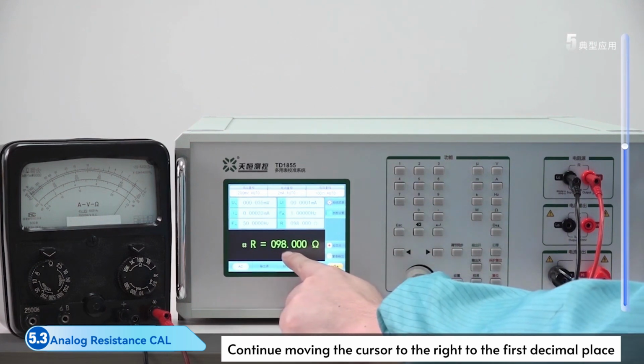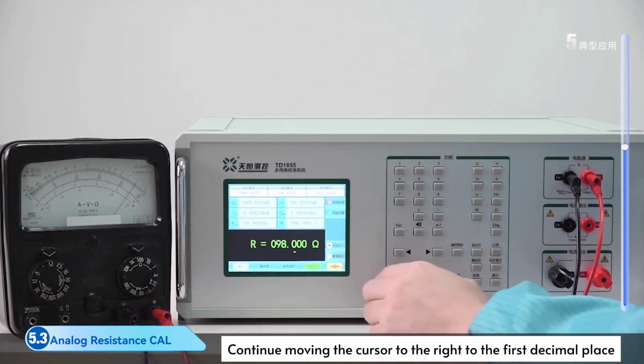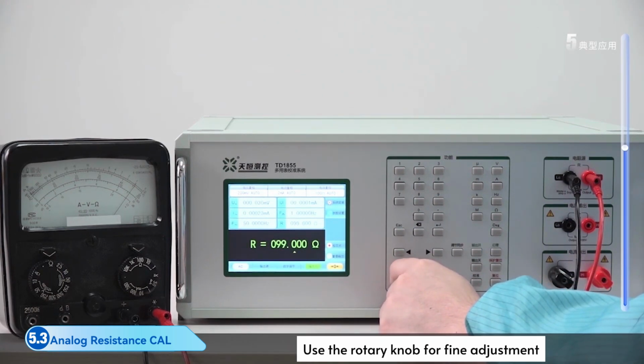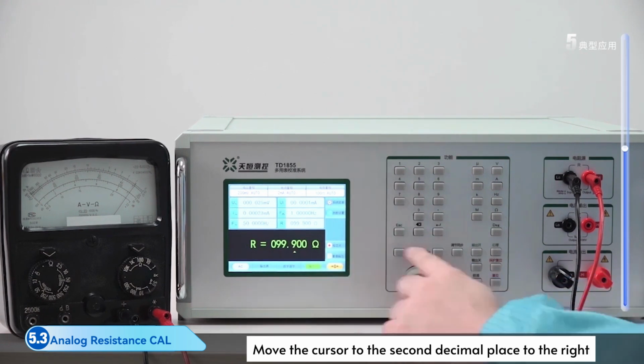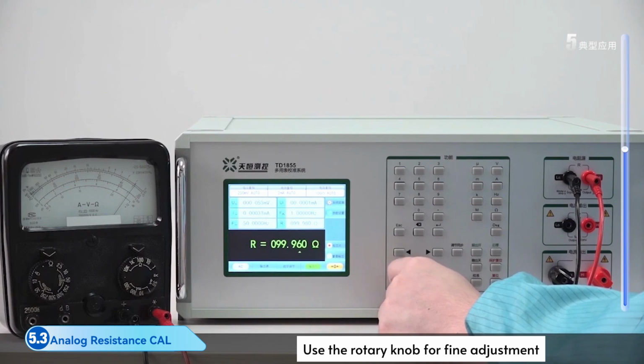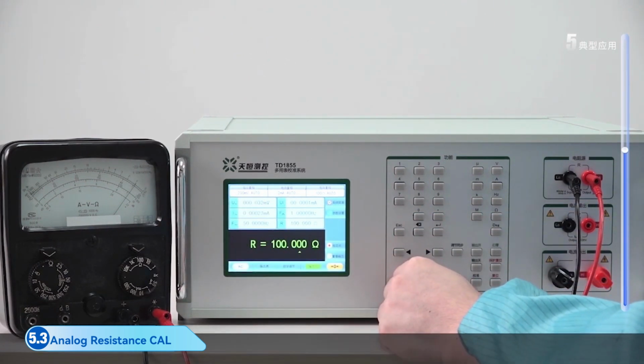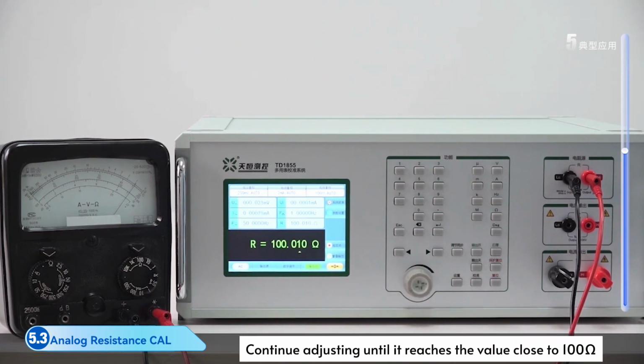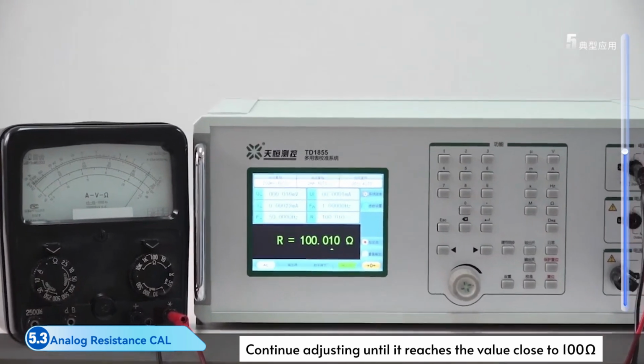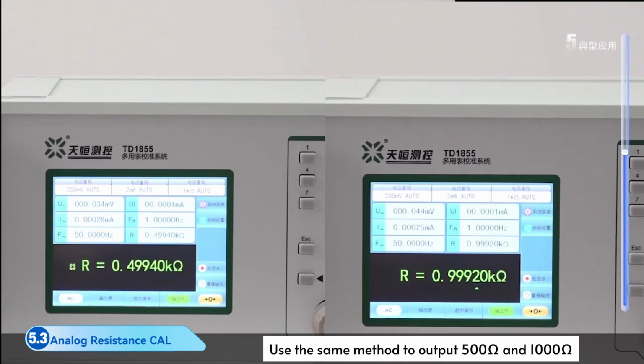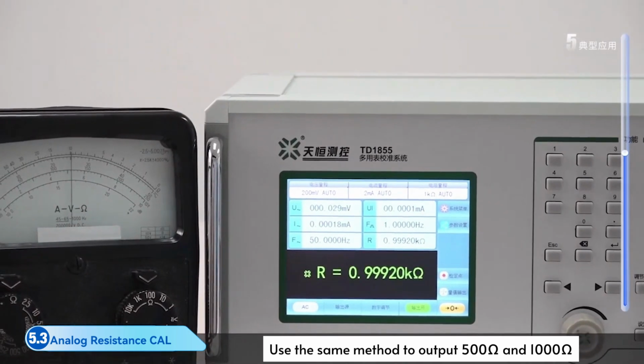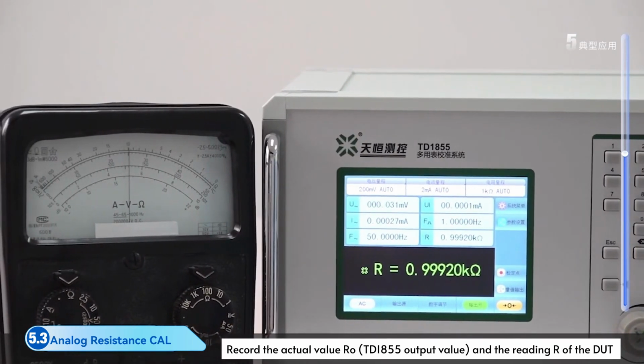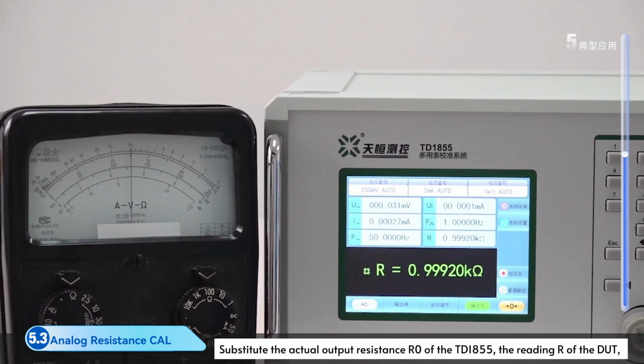Continue moving the cursor to the right to the first decimal place. Use the rotary knob for fine adjustment. Move the cursor to the second decimal place to the right and adjust. Continue adjusting until it reaches the value close to 100 ohms. Use the same method to output 500 ohms and 1000 ohms. Record the actual value and the reading of the DUT. Substitute them in the error calculation formula. Calculate the errors for each calibration point and record them in the report.